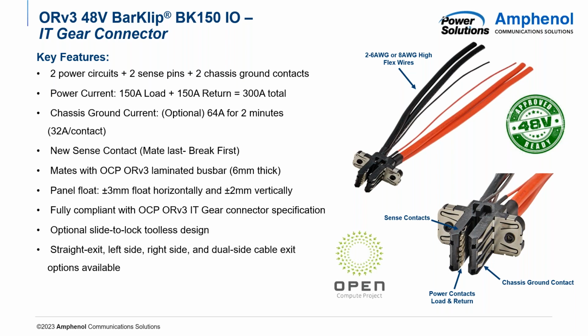We've also added additional chassis ground contacts. These contacts ground the chassis to the rack and are rated up to 64 amps for up to 2 minutes, which is double the current of the AC input connector, or 32 amps per contact per the OCP specification.